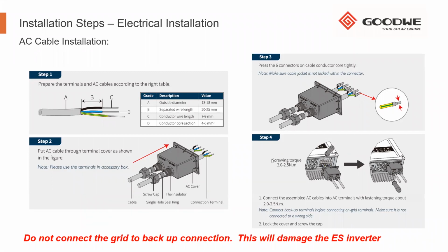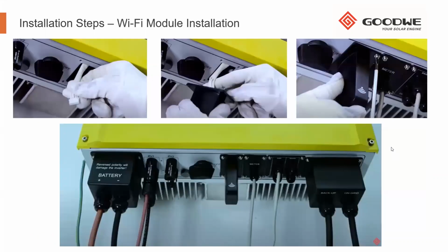You'll see the torquing of the terminals. We do recommend a 2 to 2.5 Newton meter torque, just to make sure that you don't over tighten and strip the terminals. But they are pretty resilient, and I've not stripped one myself, so they are fairly good terminals. For connecting the Wi-Fi on the ES, you'll see it is completely loose and there is a white cable hanging out. That simply gets plugged in. It can only go in one direction, and you fasten the 4 screws that hold it.